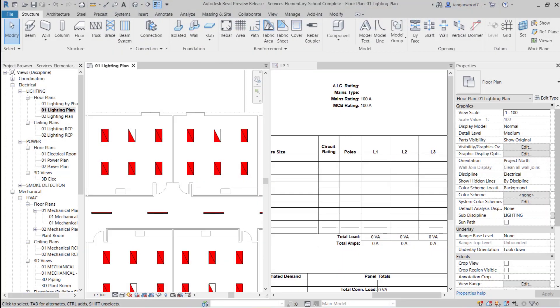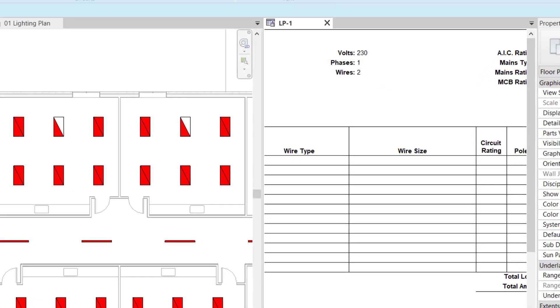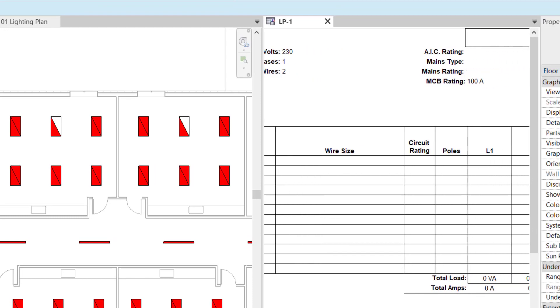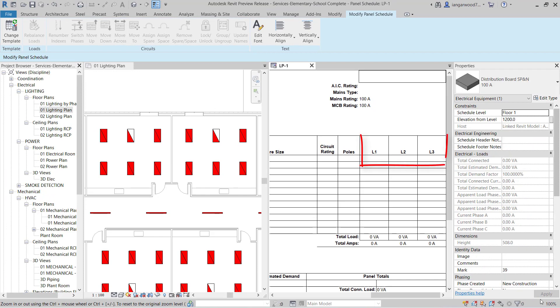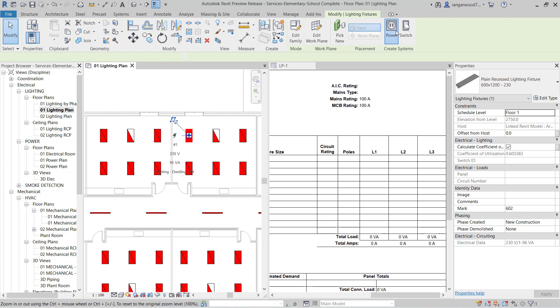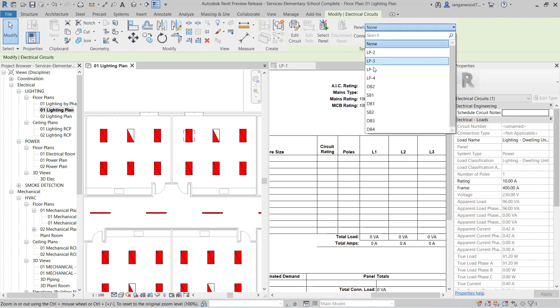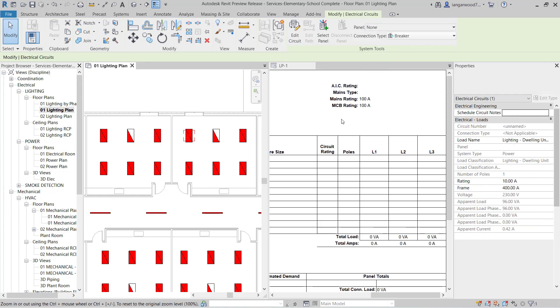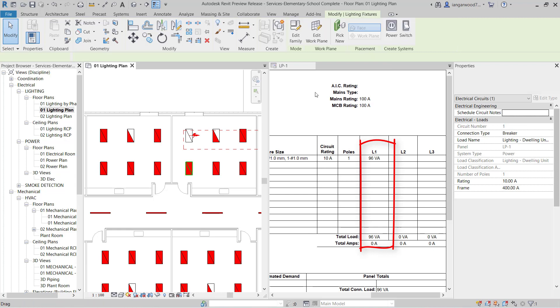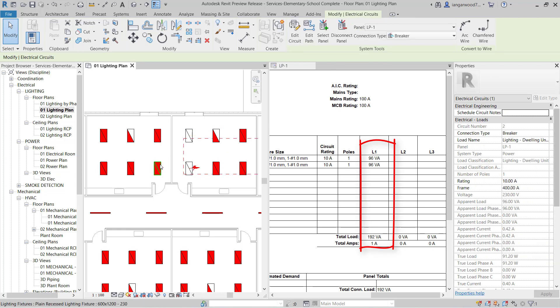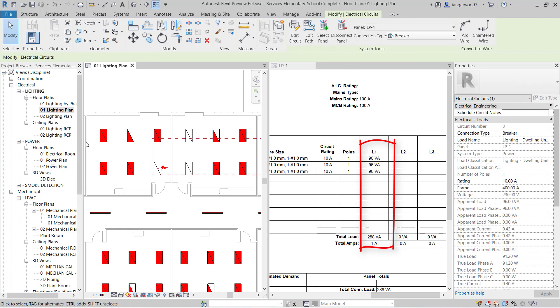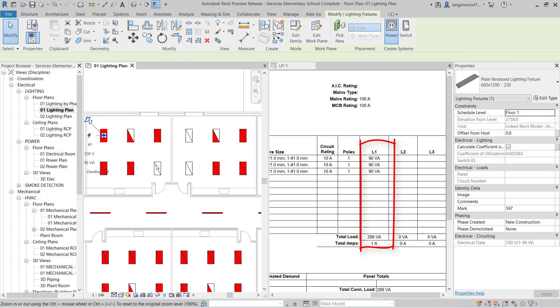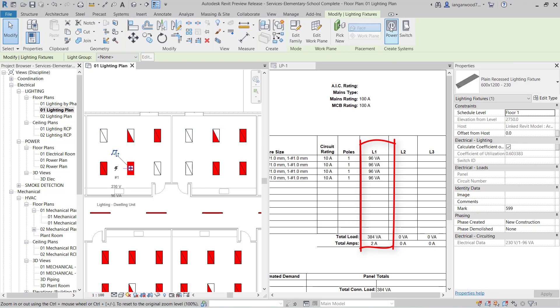In Revit MEP 2021, these have both now been addressed. Here, just for demonstration, I've set up a single-phase panel schedule but have set the display to show three phases. Unlike the results we have seen when connecting loads to single-phase panels in previous versions of Revit, loads connected to a single-phase panel in Revit MEP 2021 are all connected to the same phase, offering a more accurate view on electrical distribution within your project.